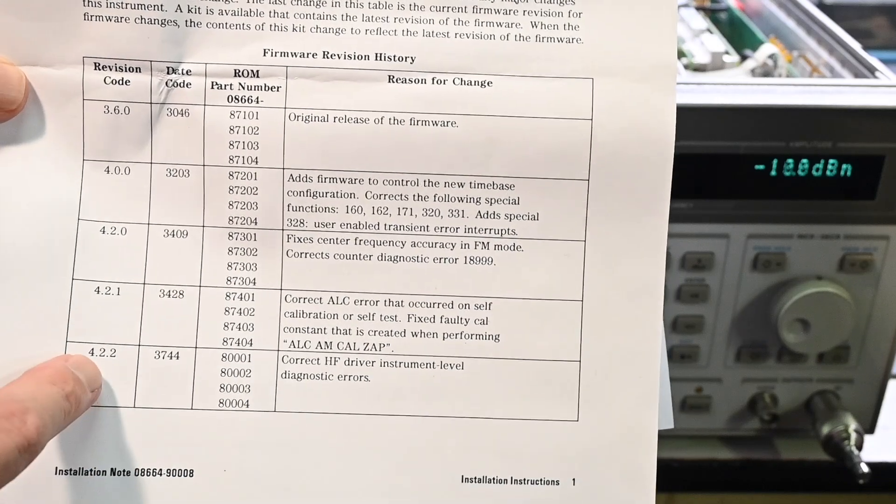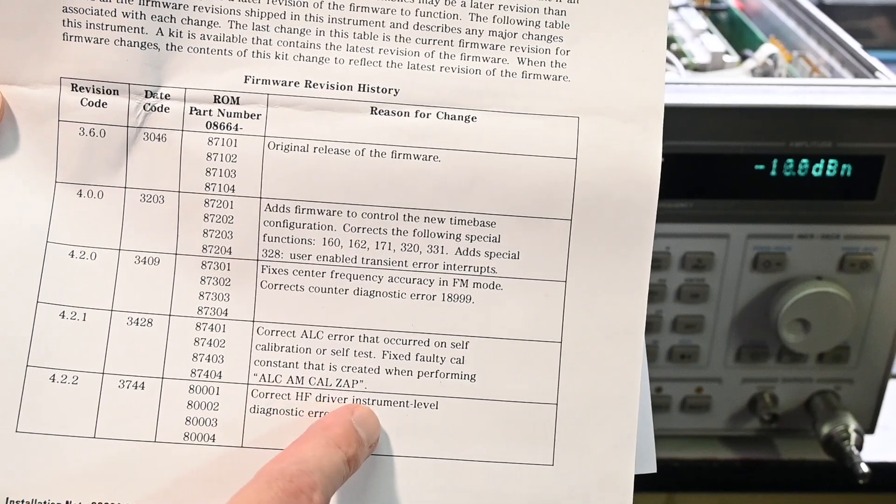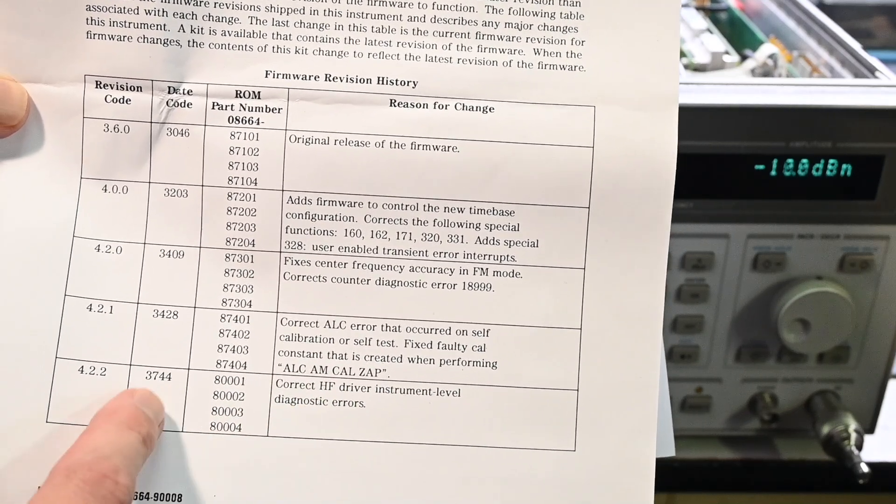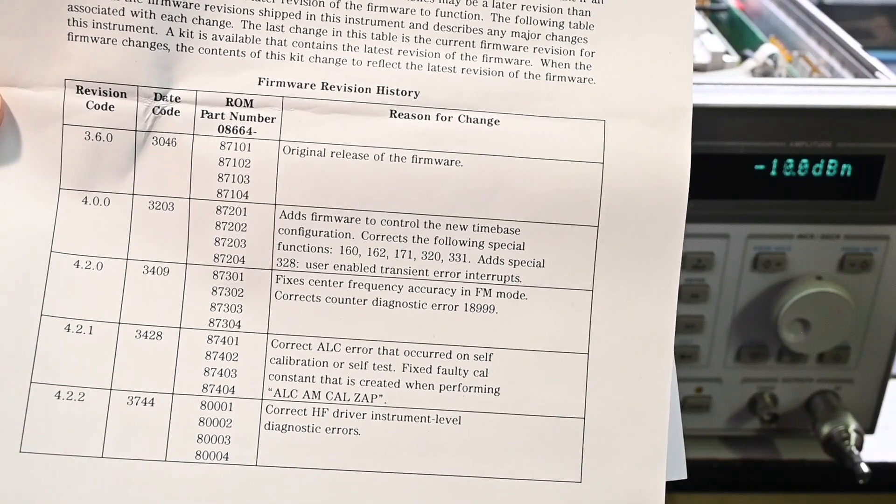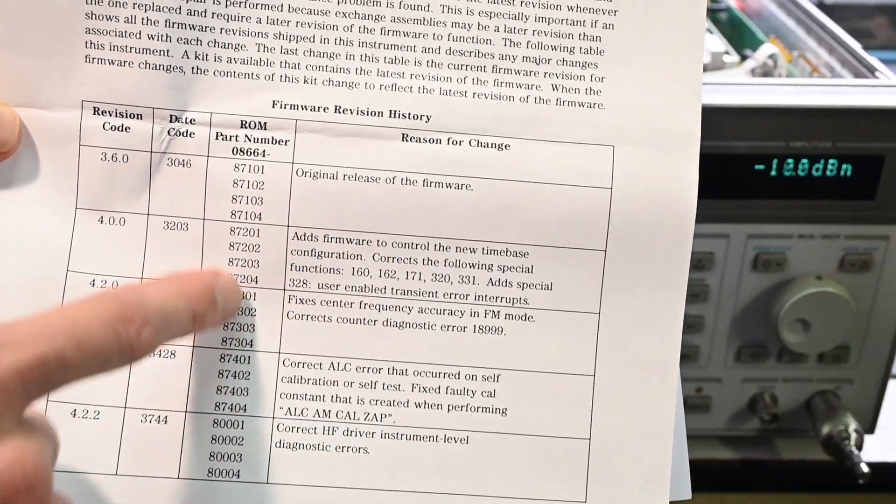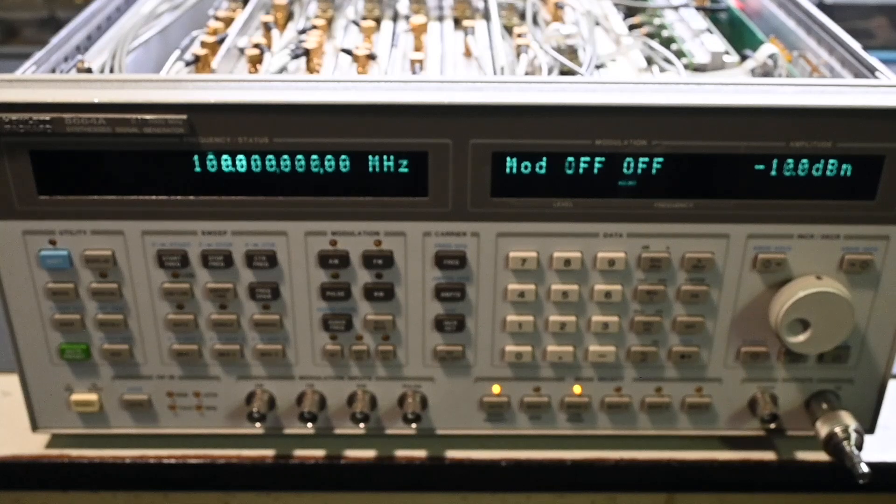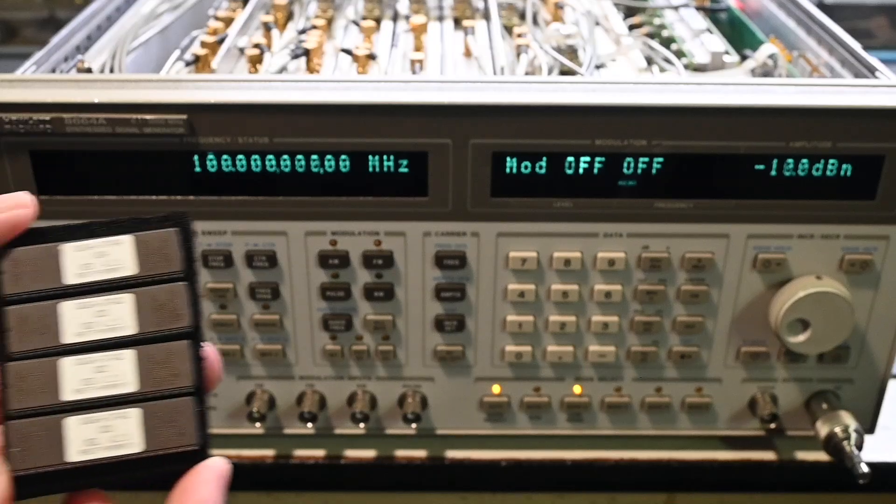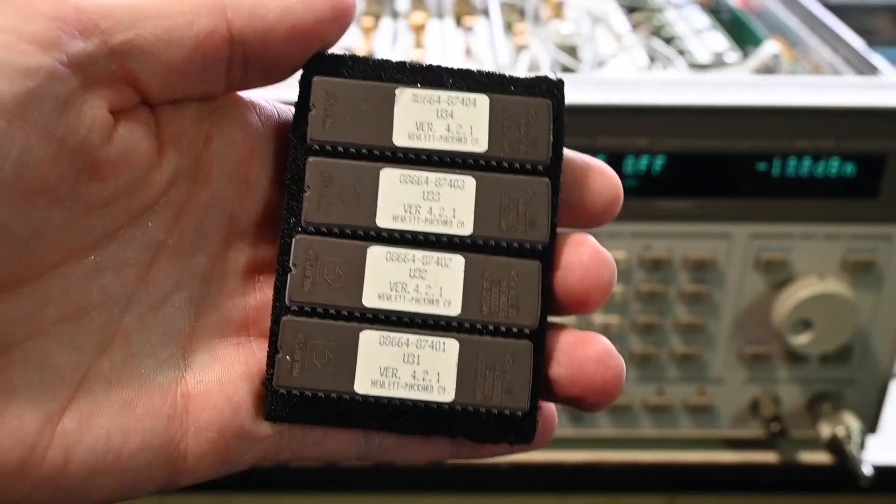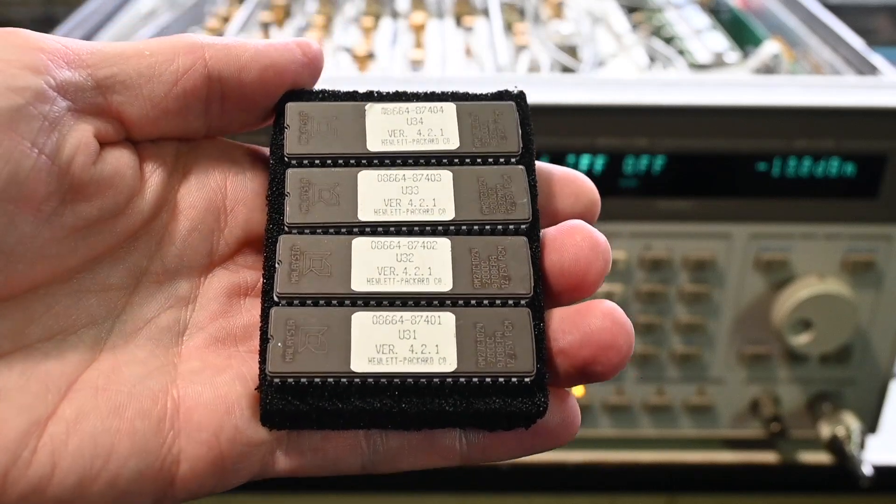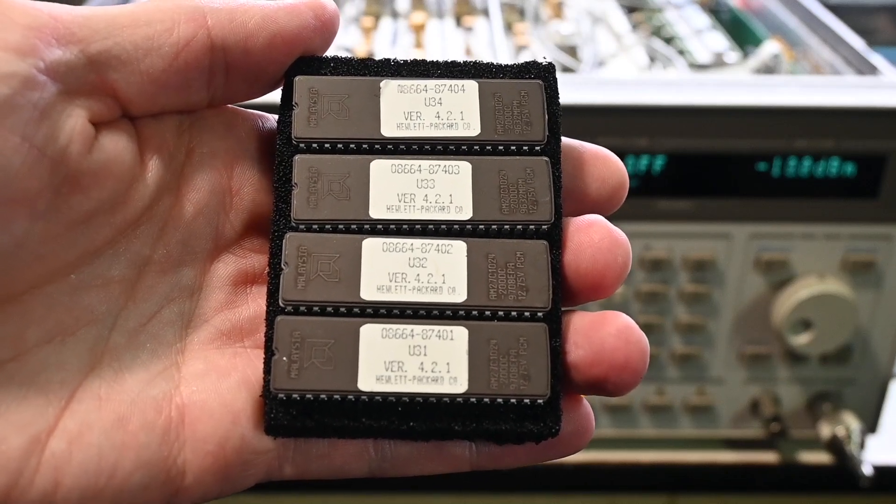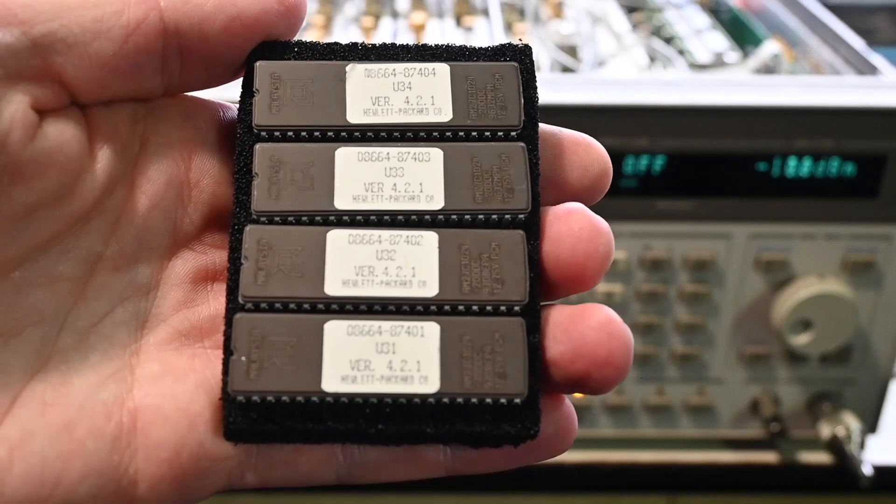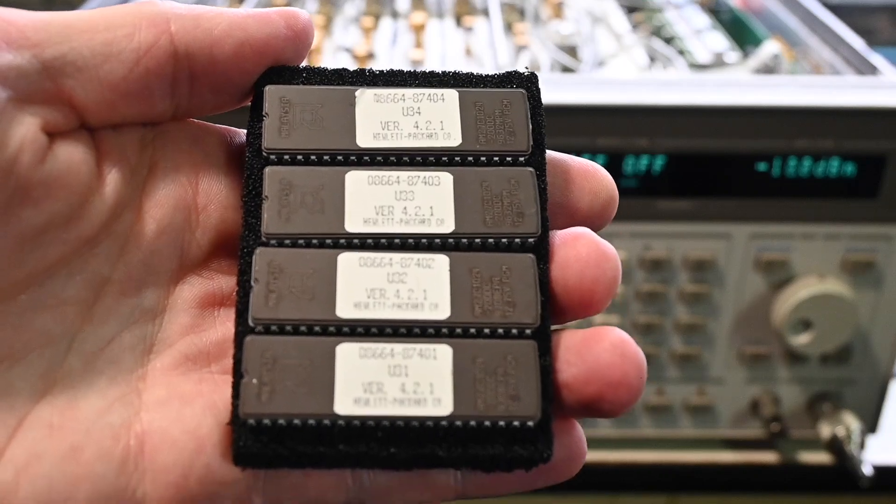So I'd like to be able to incorporate that into this instrument. So there is a version 4.2.2, but it really looks like the only change there was it corrects the HF driver instrument level diagnostics errors, and I was not able to find that version of the firmware. But again 4.2.1, I'm going to install that, so that'll take care of some of these other changes that were done. Now right here is the firmware, on these four ROMs right here. So it's a matter of unplugging the old chips and just plugging these in. So I'll get the main controller board removed, and I'll show you the old chips that are on that board, and then I'll just get these replaced, and they're in sockets, so there's no soldering or anything like that, very easy to change them out.